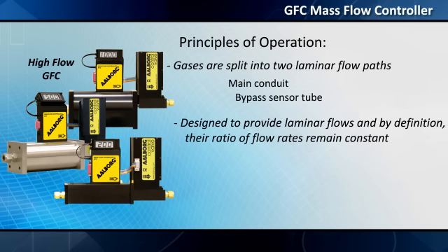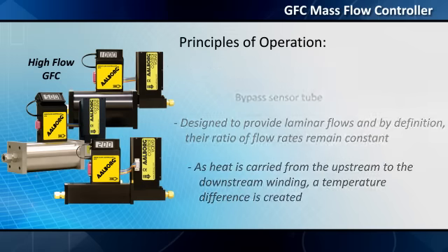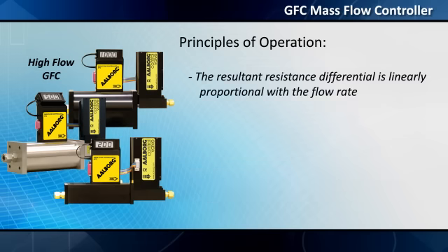Resistances of heated windings on the capillary sensor tube are monitored. As heat is carried from the upstream to the downstream winding, a temperature difference is created. The resultant resistance differential is linearly proportional with the flow rate.